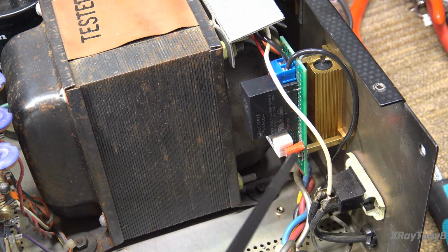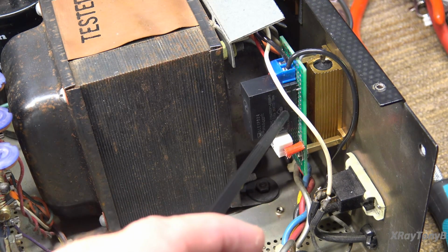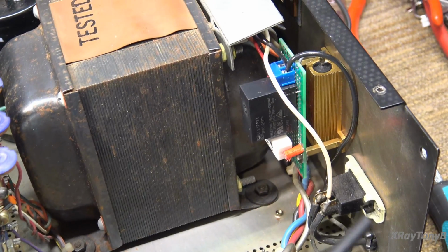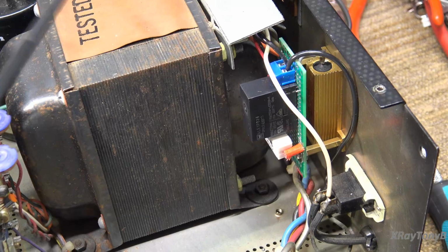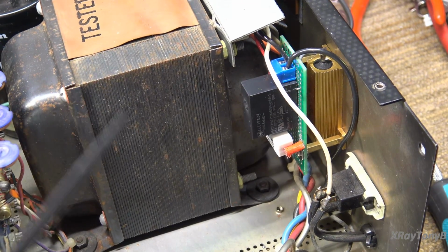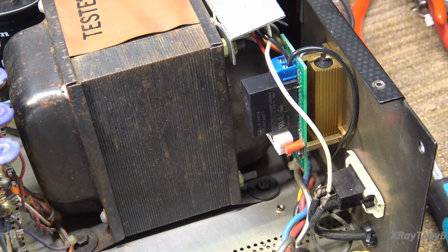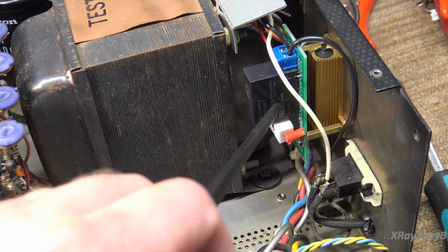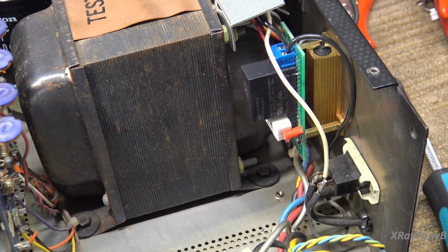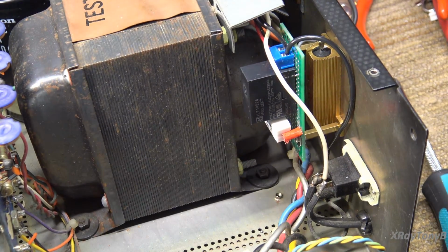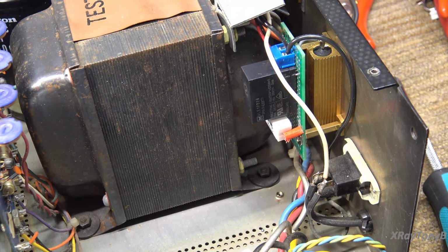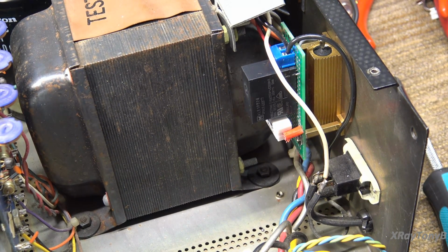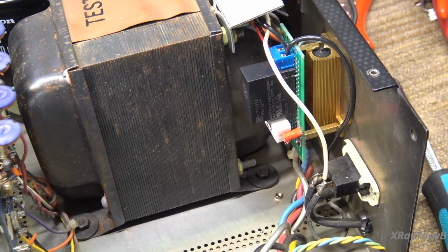They use a dropping resistor going to the coil of a relay, shunted across the capacitor bank, that is set to such a value that the capacitors have to be charged up to a certain level and the current down to a certain level before the relay will come in and close out this resistor here. So nothing to worry about. Hope that sets your mind at ease about all that.